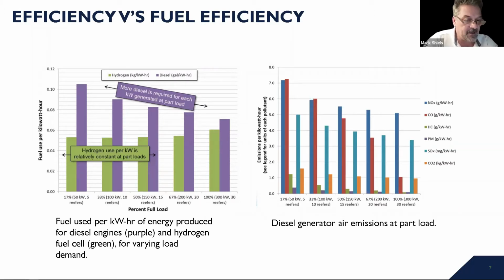The fuel burn of a diesel generator increases as the load is reduced, which is not what you would expect. While with a fuel cell, if the load is increased or reduced, the fuel consumption remains relatively constant against the load itself.